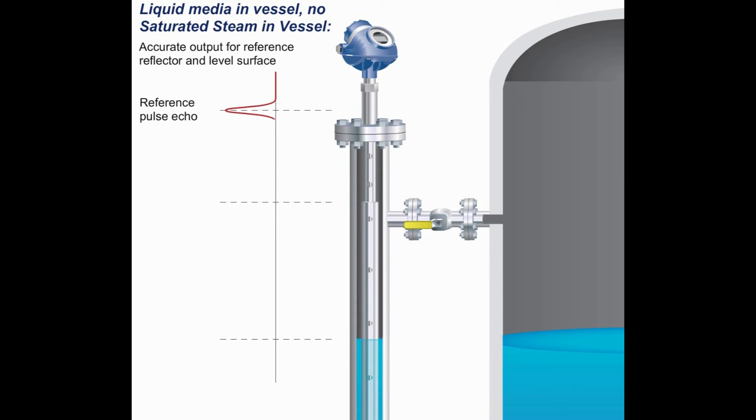A reference pulse echo can be seen just above the flange. This echo is derived from where the dynamic vapor compensation probe meets the pressure seal. A dimensional difference in this section provides the echo.